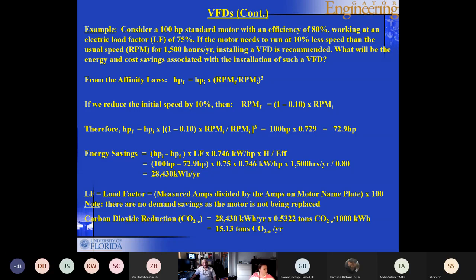And as a consequence, your energy savings is going to be the difference in horsepower multiplied by the load factor, multiplied by the conversion from horsepower to kilowatt, multiplied by the number of hours, divided by the efficiency. And if you do all that, you're going to get about 28,430 kilowatt hour per year. Here again, I'm listing for all of you that the load factor is the ratio between the measured amps divided by the amps on the motor nameplate multiplied by 100. In this case, there are no demand savings, even though you reduce the demand, because you have not really replaced the motor. So the motor is still there, same motor. The carbon dioxide reduction, of course, can be calculated as usual, multiplying it by 0.5322.